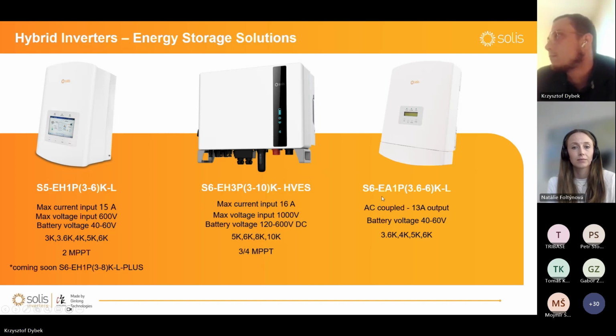And this guy, I will tell just a few words about it because this particular device is not really interesting for the Czech Republic market, I suppose. This is AC coupled. So we also have single phase AC coupled and newer S6, like this guy. Single phase inverters without any PV input designed for retrofit scenarios. When you already have a working system with an inverter and solar panels, but your inverter is not hybrid and you want to add also a battery. So it doesn't matter which brand you already have. AC coupled works with any other inverter as there is no communication between them. You only need to install this inverter, a power meter, which comes in the box to measure export and import from the grid, and of course a battery from one of our compatible manufacturers.